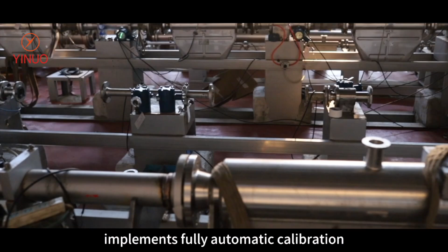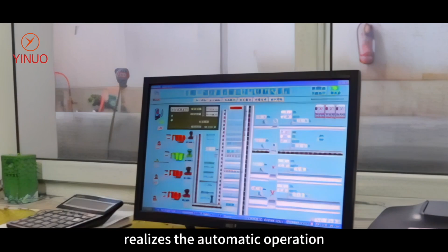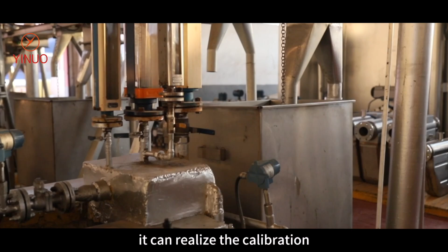The water calibration device, like the oil and gas calibration device, implements fully automatic calibration. The hardware construction and software development of the device are independently researched and developed by our company. The automatic calibration device realizes automatic operation in the calibration process through computer control, and can meet calibration requirements for different flow meter accuracies such as 0.1, 0.2, and 0.5.